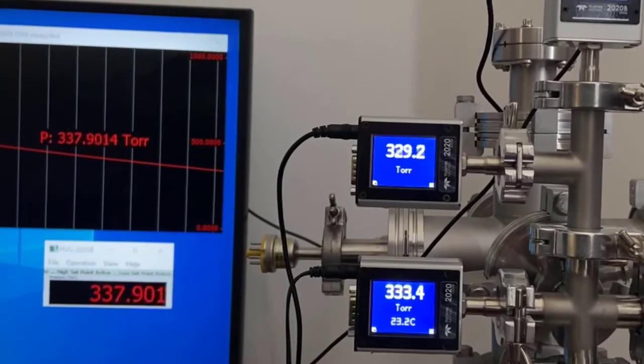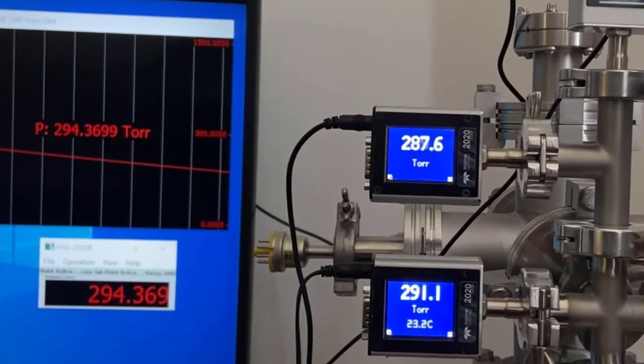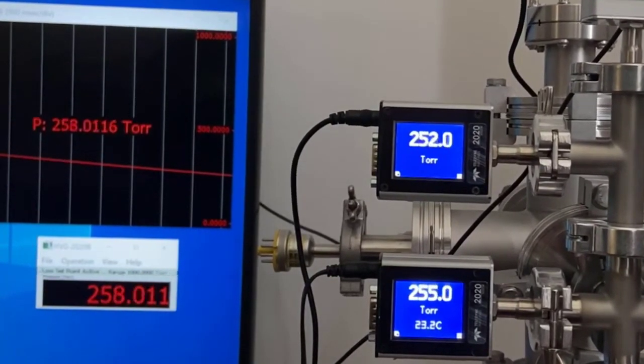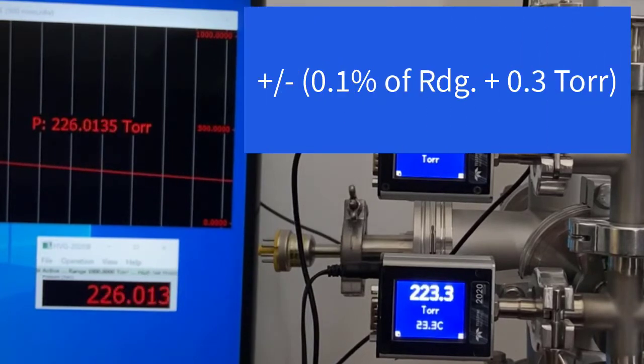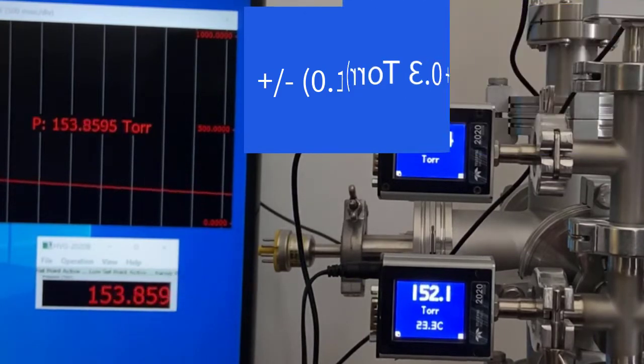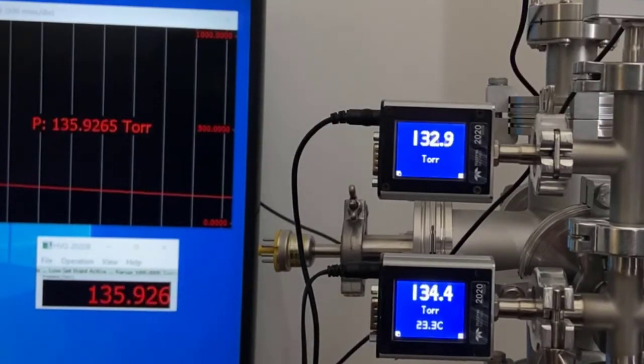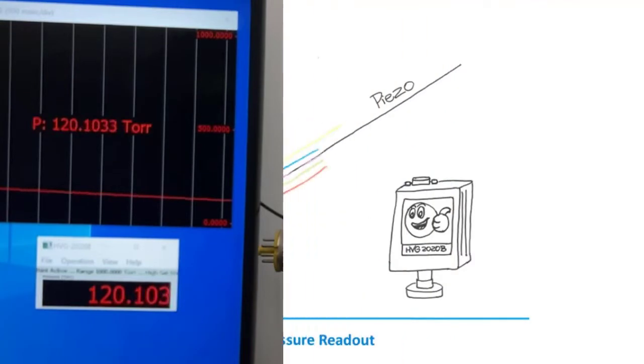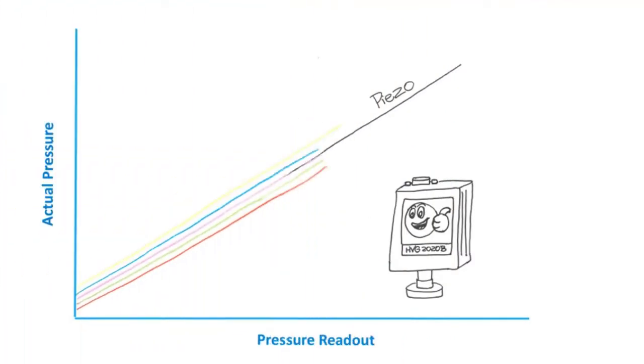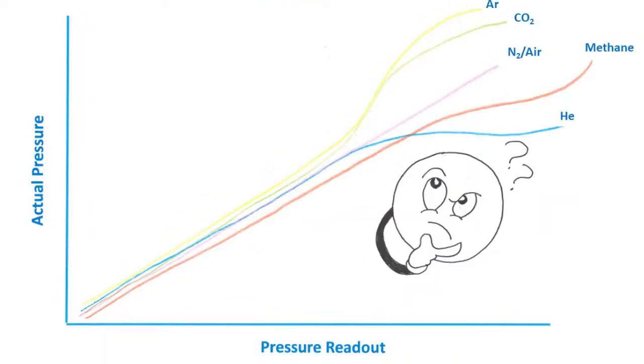Now, the piezo sensor allows us to do a couple of things. First, this sensor is very accurate. The accuracy above 20 torr is plus or minus 0.1% of reading plus 0.3 torr. But equally important is the fact that the piezo sensor's output for a given true pressure is not affected by the composition of the gas. Note that convection-driven Pirani gauges are strongly dependent on gas composition as the pressure is increased towards atmosphere.